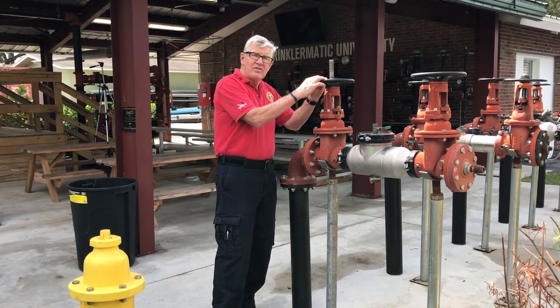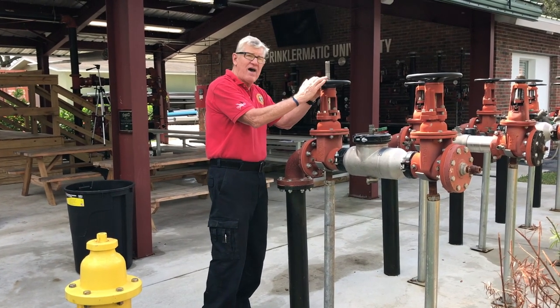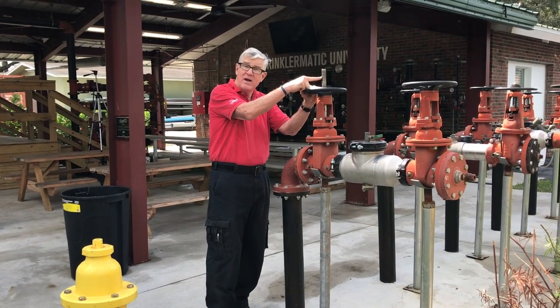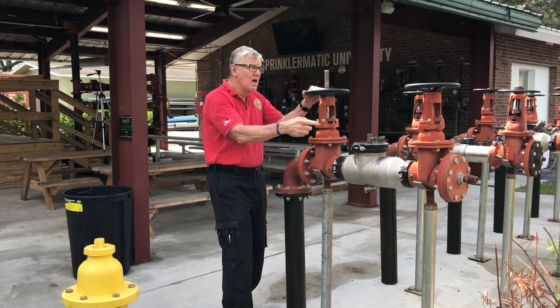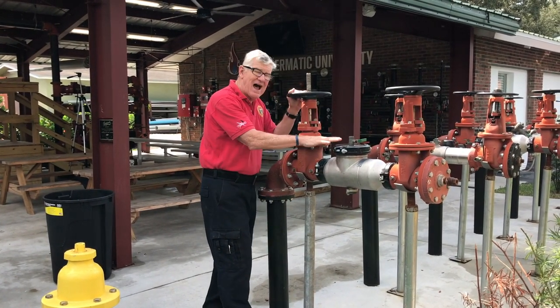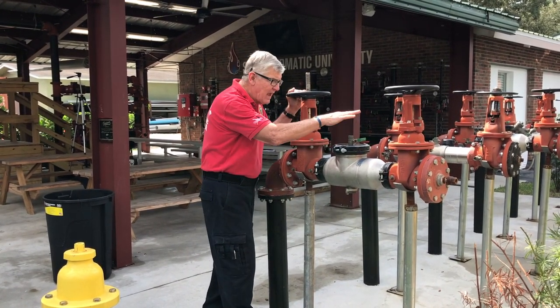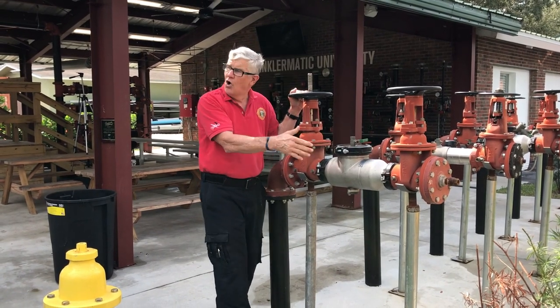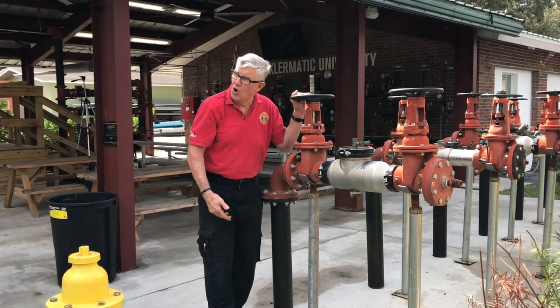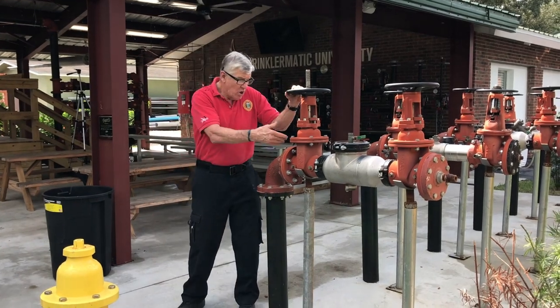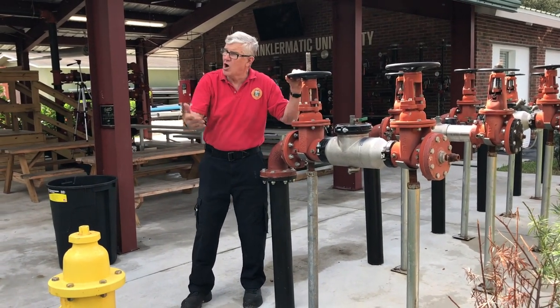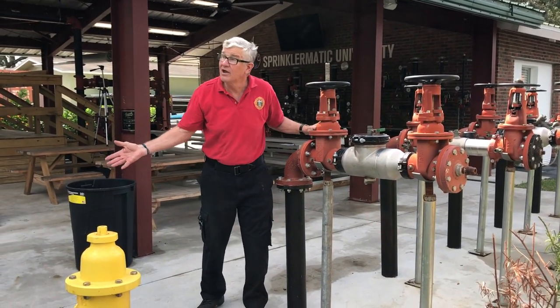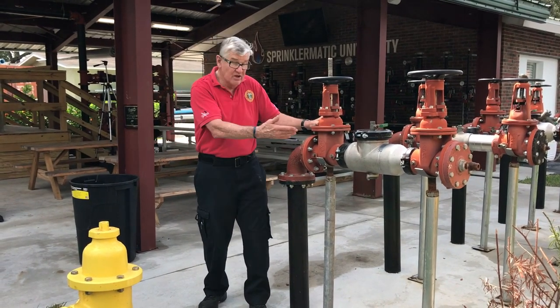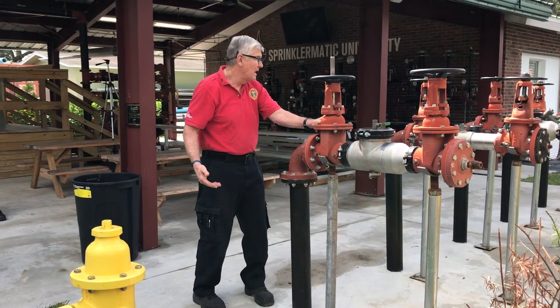The reason for the outside stem and yoke valve, this one of course being open, you can see because of the stem, this one being closed, is to isolate this valve so that we can service or replace the backflow prevention device. Now, you will not see this in Chicago or Minneapolis because it would be frozen in the wintertime. This will be in the basement.